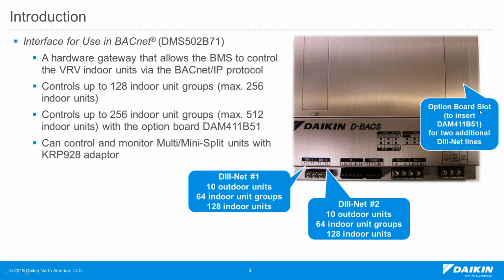It also has an option board called DAM411B51 available. With this option board, which can be inserted in the gateway directly into this slot, it expands the gateway's capability to control two more DIII-Net systems. That means that with this option board, one gateway can control up to 256 indoor unit groups and a maximum of 512 indoor units. The interface for use in BACnet can also be used to control and monitor the residential products, the multi-split and the mini-split units, with the KRP928 adapter. This adapter is needed for each individual indoor unit.